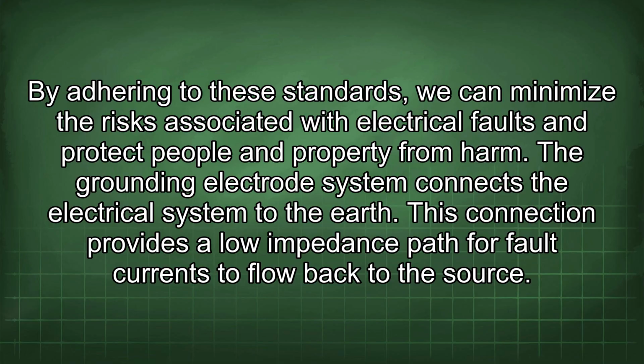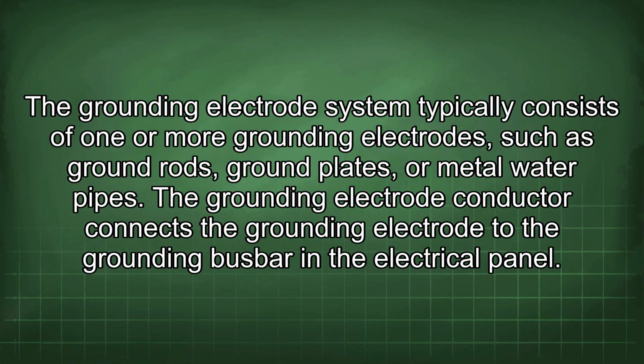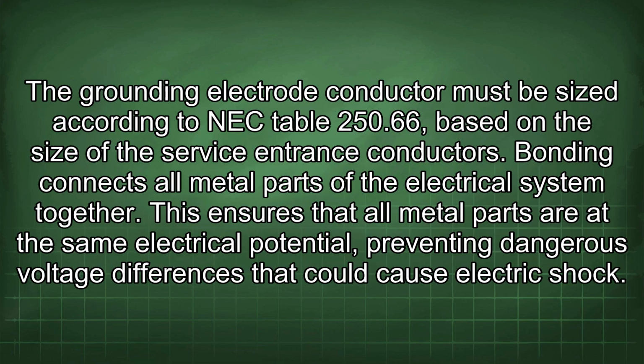harm. The grounding electrode system connects the electrical system to the earth. This connection provides a low impedance path for fault currents to flow back to the source. The grounding electrode system typically consists of one or more grounding electrodes, such as ground rods, ground plates, or metal water pipes. The grounding electrode conductor connects the grounding electrode to the grounding busbar in the electrical panel. The grounding electrode conductor must be sized according to NEC Table 250.66, based on the size of the service entrance conductors.